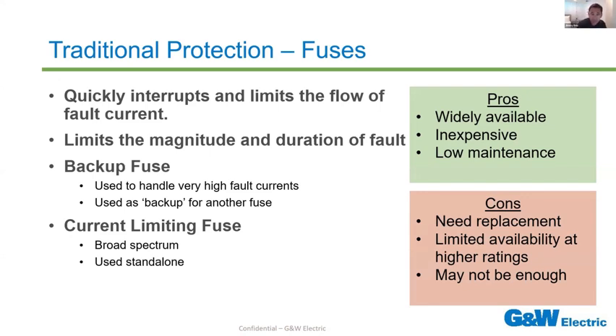So now let's talk about the traditional protection used to counter these fault levels in your systems. One of them being fuses, which we are all very familiar with. They quickly interrupt and limit the flow of current, and they do so by limiting the magnitude and the duration of the fault. Two examples of those are backup fuses, which, as the word states, back up another fuse and are used to handle very high fault current levels. And another one is the current limiting fuse that can also be standalone, and by definition, they're current limiting, so they limit current to under half an electrical cycle.